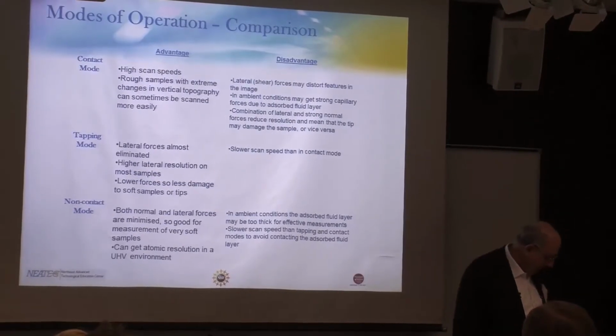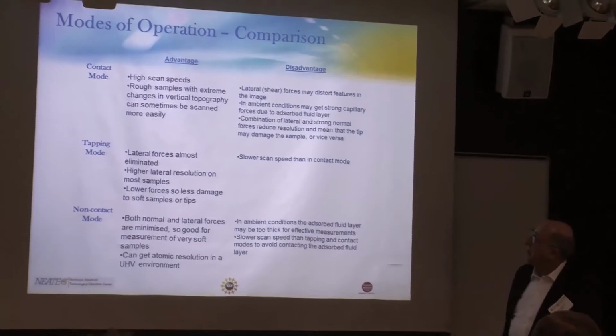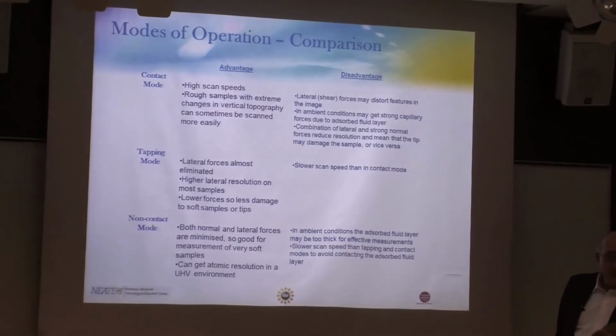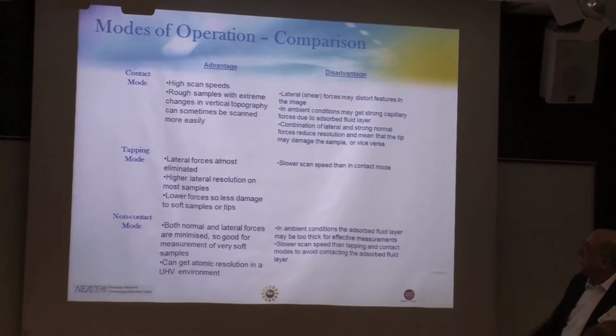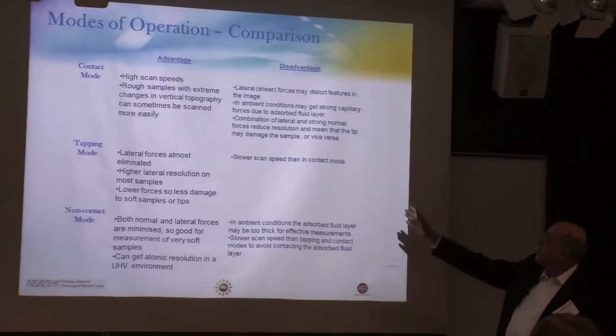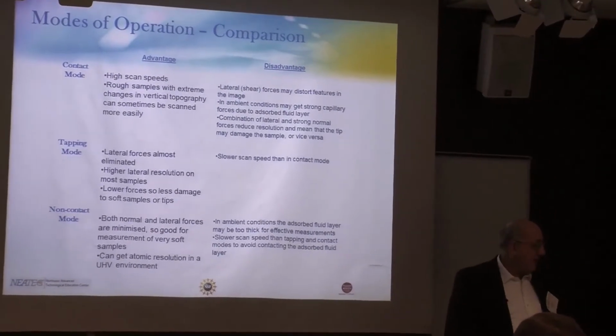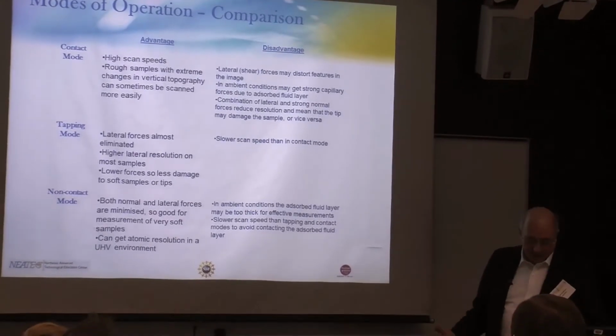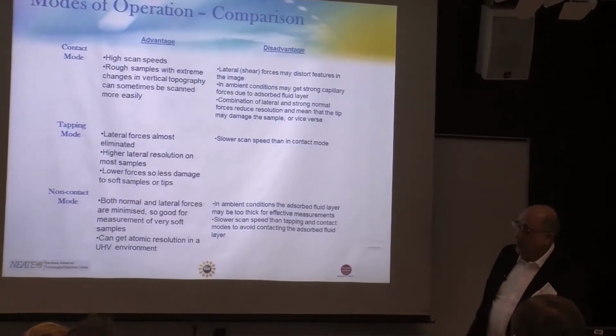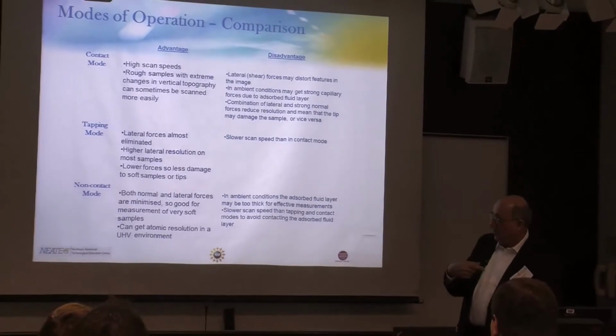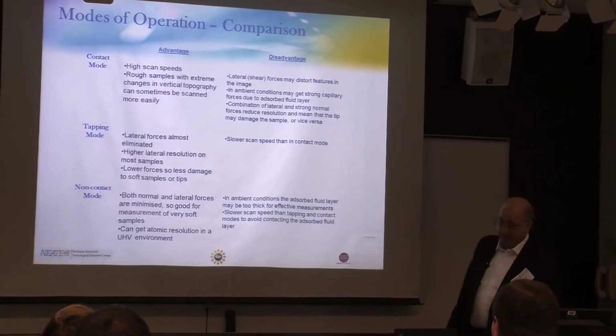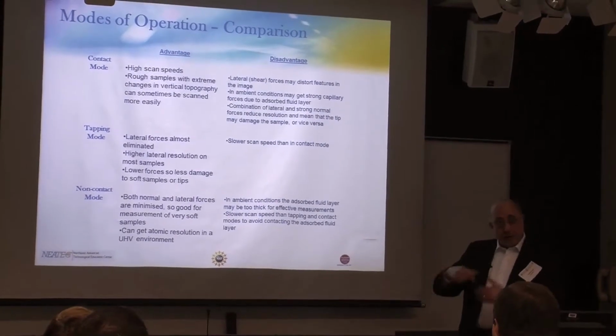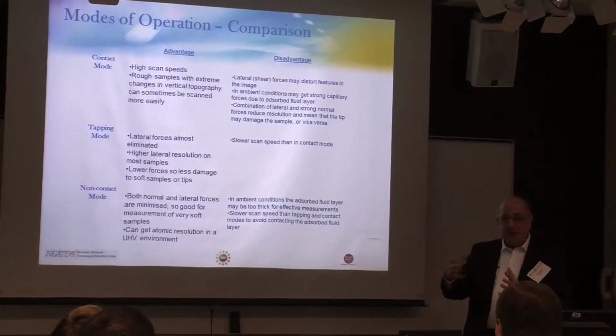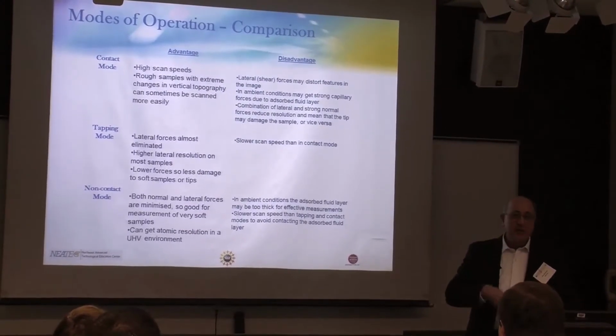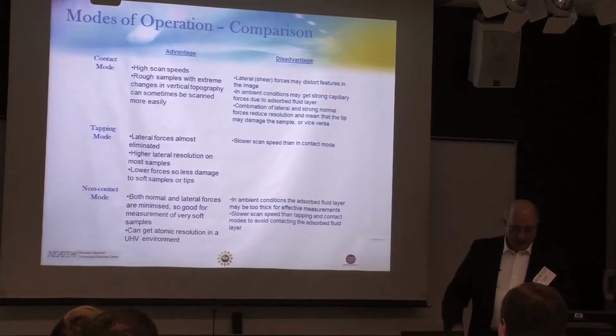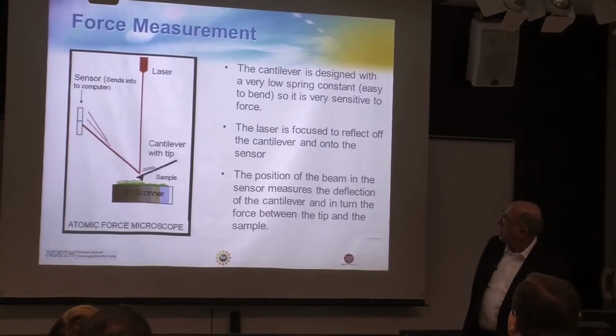Here you have a little table about the advantages and disadvantages. You can see that tapping mode has the fewest disadvantages, but it is probably a little bit slower, but it's okay. This is what we do here today. We're going to do the measuring with tapping mode, and you will see in the computer the frequency and the phase and everything being calculated.